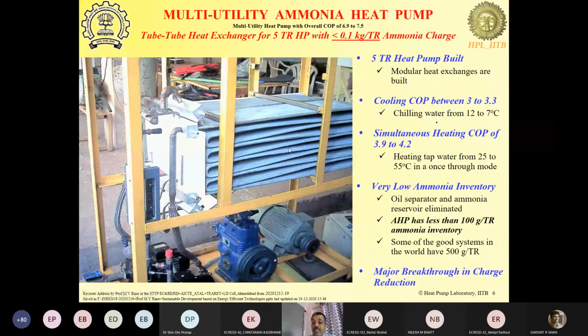And of course, we are generating two utilities from the same system. You don't need a separate heat pump to generate the hot water, and you don't need a separate chiller to produce the chilled water. A single system producing both would certainly reduce the charge, because the charge in two systems is going to be much more than in a single system. Plus, of course, the energy consumed is less, so your CO2 emissions are reduced as well.